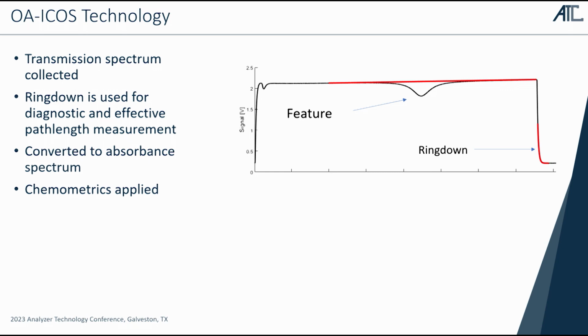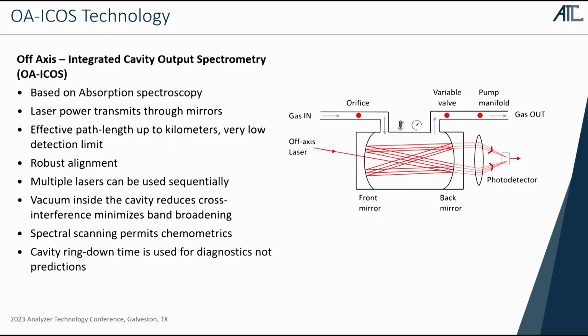We scan this laser, excuse me, I hit the wrong button. We scan the laser continuously. There's no stopping it. We'll pulse it sometimes, but we scan it so we can collect an entire spectrum. Now the spectrum's only going to be a nanometer, 2 nanometer spectral region, but you're looking at the fine structure of an absorption band, and this permits multiple components, if they appear in the same spectral region, to be measured at the same time.